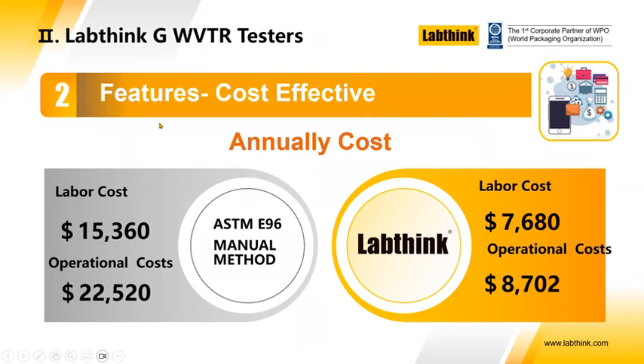So I said it was cost effective. Here are some examples using some data which we've collected from our own experience and from that of customers, comparing the manual method on the left and the automatic Labthink methods on the right. As I mentioned, the labor cost will be lower because the operator's involvement is virtually nil apart from preparing the specimens. And also the chamber and its control has been designed specifically for the number of specimens that will be used. So instead of having a very large chamber, which uses a lot of electricity, a lot of energy cost involved in running that chamber, the Labthink instruments have a very small energy demand, and so the cost is very minimal for using them, and also the cost of replacement parts and such like is very small. So quite a potential cost saving, at around 60%.